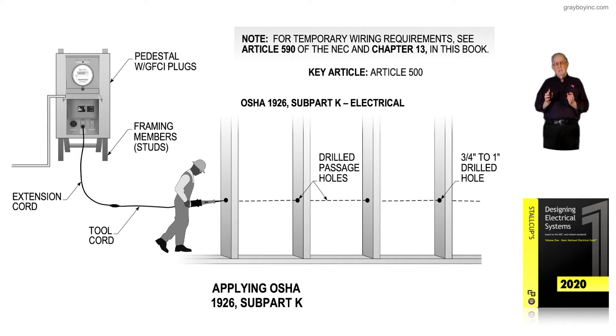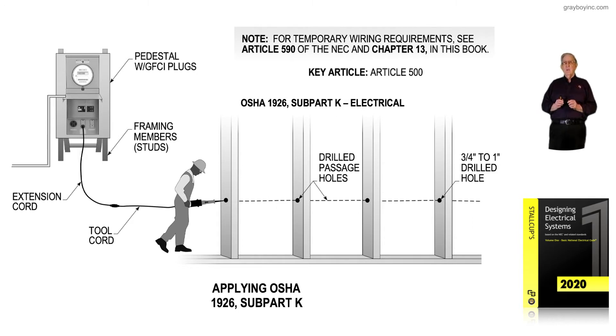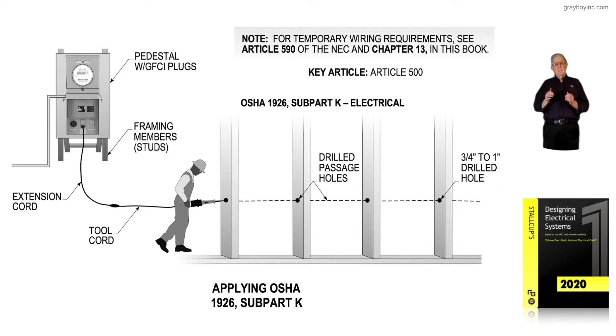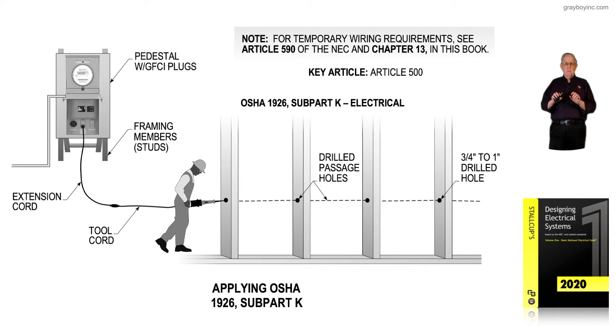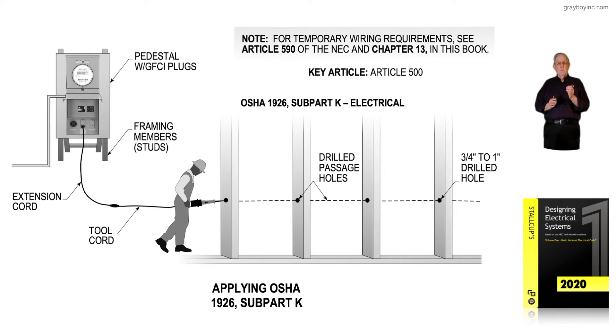The framing members can be used as supports to support the cable or wiring method. Notice this is temporary wiring, so the key article would be Article 590. Article 590 deals with temporary power construction regulations that are less stringent than the wiring methods for a particular piece of equipment or installation. The only thing that Article 590 requires to meet Article 230 would be the service equipment that's feeding that pedestal.